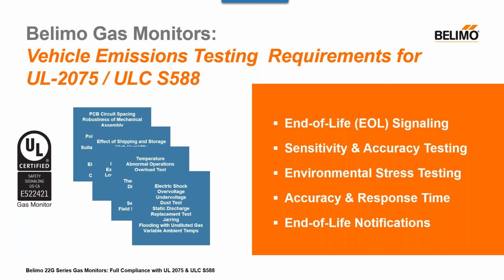Also, environmental stress testing, especially in the different regions throughout the Americas. Gas monitors certified under UL 2075 must demonstrate reliable performance under variable environmental conditions, such as high humidity, temperature changes, and voltage fluctuations. These tests ensure that the device can operate effectively in real-world applications where conditions are often less than ideal.